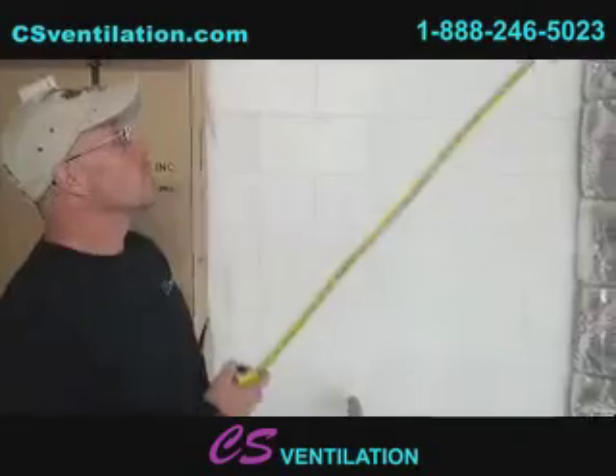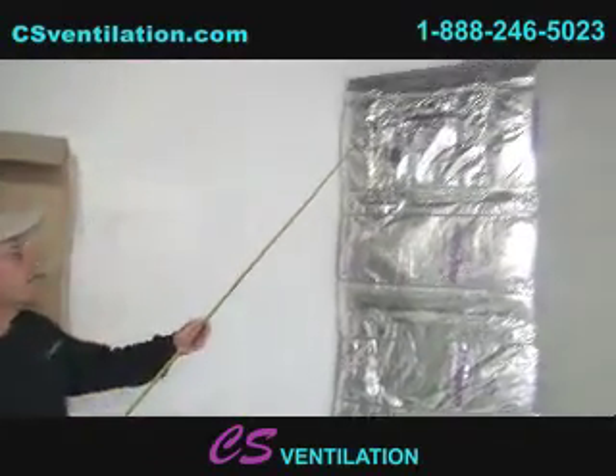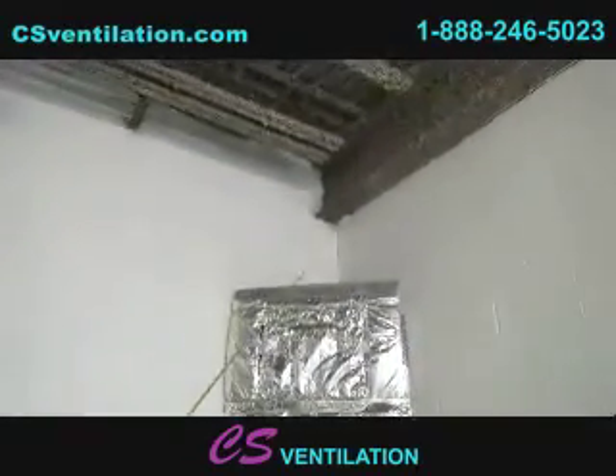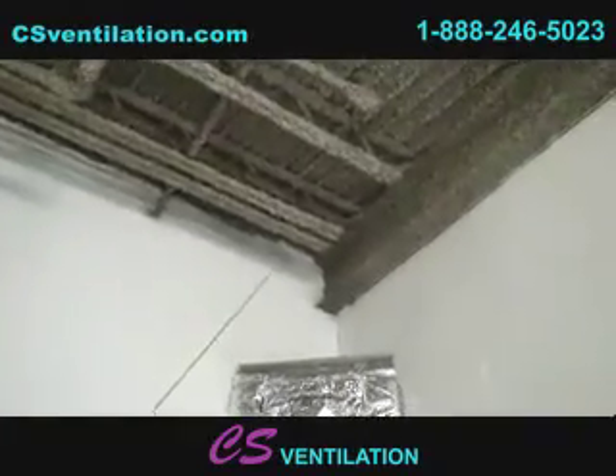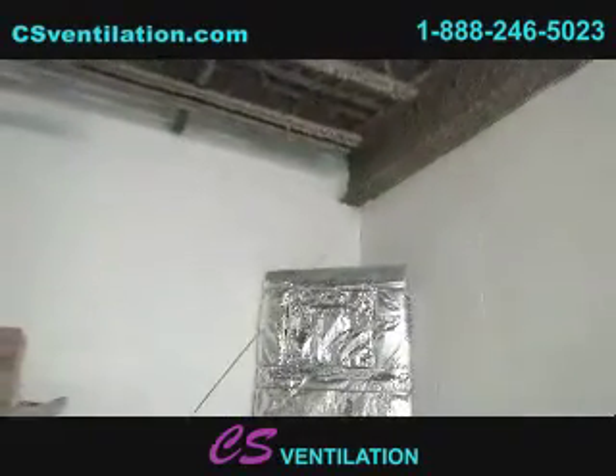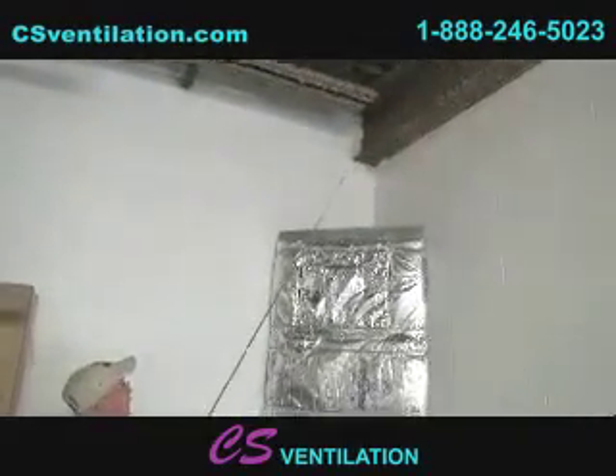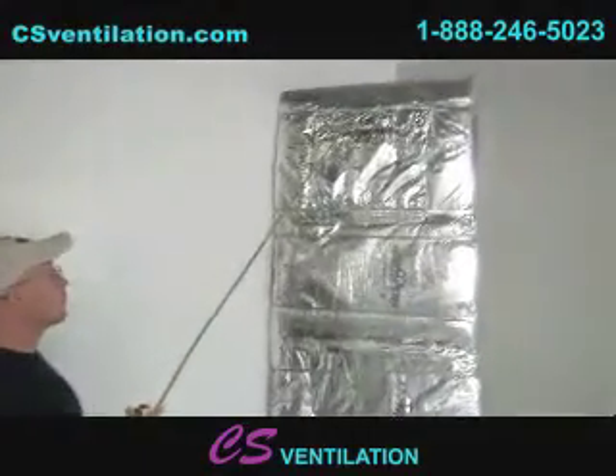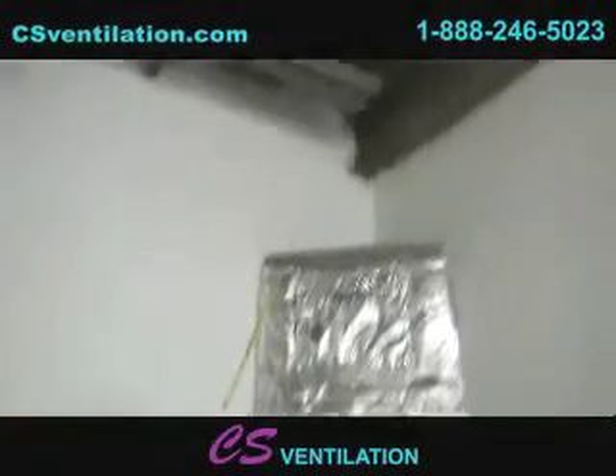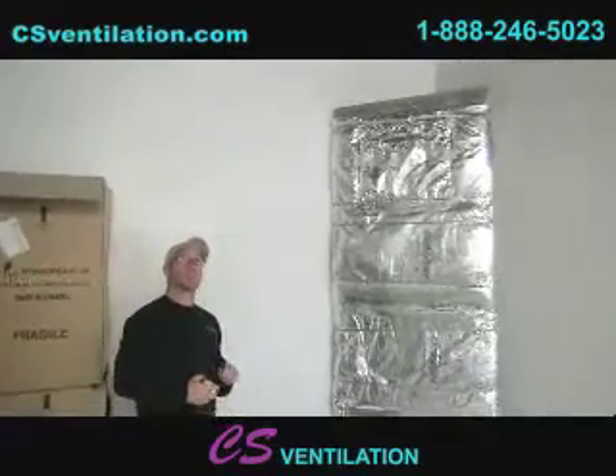We're at the roof, or right below the roof, and we're unable to run this triangle ductwork straight up because we've got our cross beams, our support beams in here, so we would crash out on this. What we need to do is offset this ductwork, come up 90 back this way, approximately about 10-12 feet, then go through the roof.